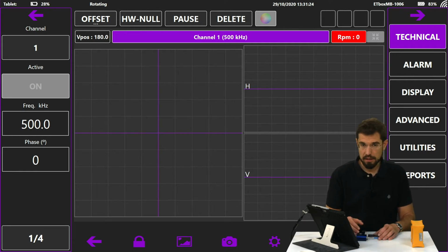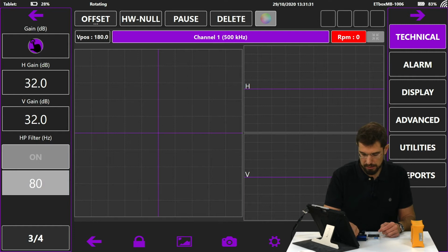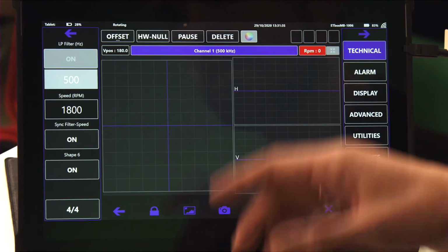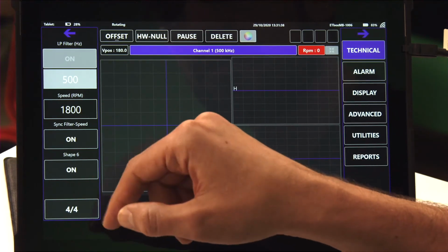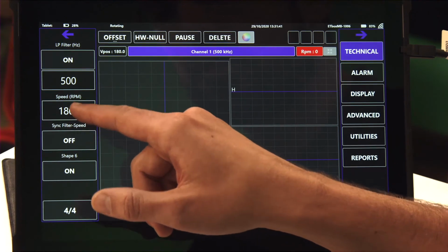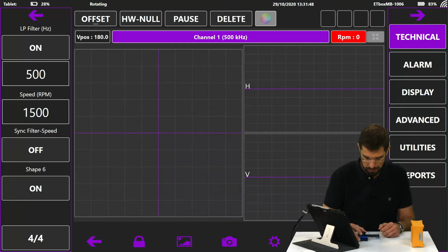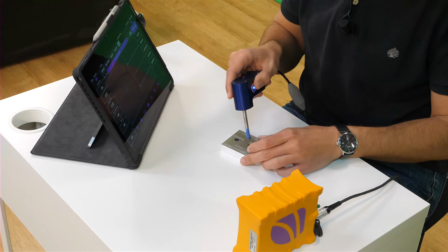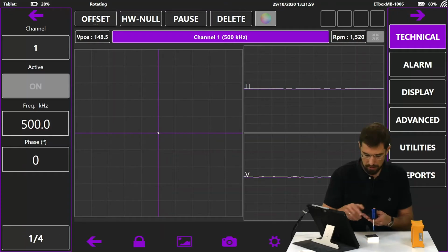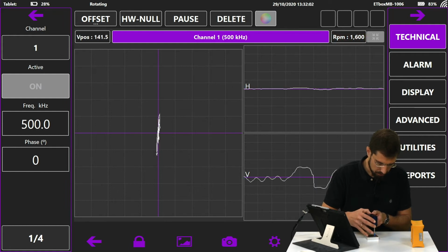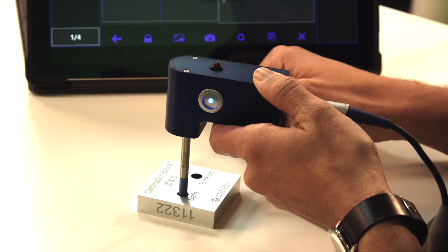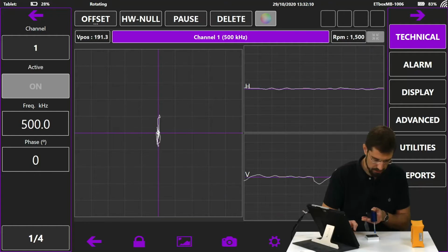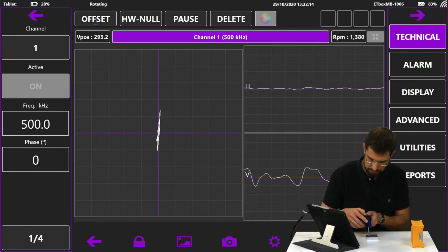Knowing this, I am going to focus on the parameters that differ from the other application. First, when we do this inspection, we must always check the rotation speed at which we want to make the acquisition. Right now, it's set at 1,800 revolutions per minute. We see we can change it and set it. Let's set, for example, 1,500. And now we can pull off the probe sleeve to make an acquisition. Like all eddy current calibrations, in the first place, we're going to get in the safe zone. We're going to do a hardware null. Okay, and once we have centered the signal, we can acquire the board that has the notch in it.